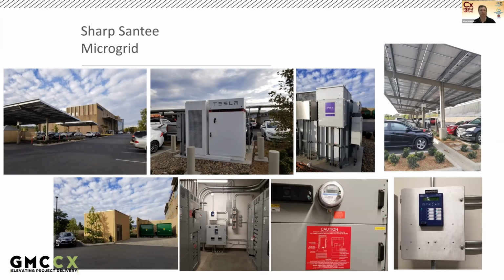Here's another picture of the solar panels above the parking area with the inverters. Behind the building, back behind here is the generator, the 100 kilowatt diesel generator in a separate structure. Inside, on this side of the building, is the electrical room, which houses the motorized breaker panel with CB1, CB2. There's also other meters here. This is the main utility meter. And this is a picture of the non-export relay.